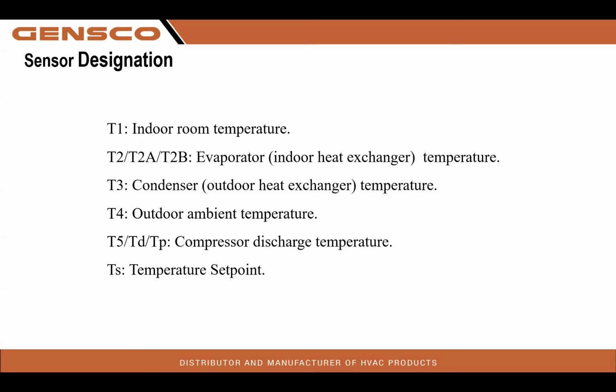And by the way, since we're going to talk about the outdoor ambient temperature sensor, if the outdoor temperature is between 79 and 83 degrees and you give this unit a call for heating, it will not like that, and it will block the heating call to the outdoor unit. It will not energize that reversing valve, to protect itself from going off on high head pressure in 3 to 5 seconds. And T5 is our compressor discharge temperature.